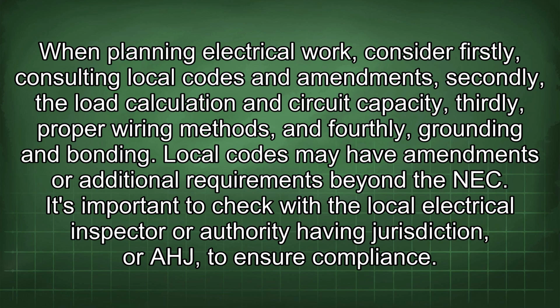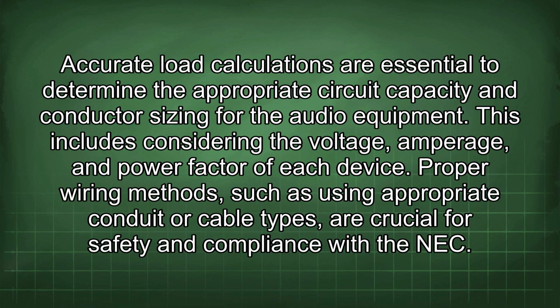Local codes may have amendments or additional requirements beyond the NEC. It's important to check with the local electrical inspector or authority having jurisdiction, or AHJ, to ensure compliance. Accurate load calculations are essential to determine the appropriate circuit capacity and conductor sizing for the audio equipment. This includes considering the voltage, amperage, and power factor of each device.